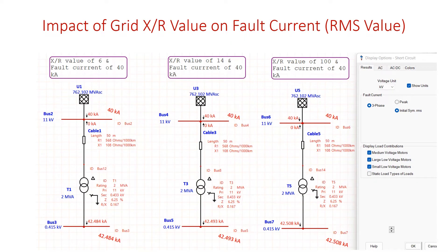In order to understand the impact of grid X by R value on fault current, I have chosen one simple ETAP model where the grid is with X by R value of 6, fault current of 40 kilo amps. I have provided one cable that connects transformer, cable with the length of 50 meter, R1 X1 value displayed here. The transformer is a 2 MVA transformer, primary with 11 kV, secondary with 0.433 kV. Impedance of the transformer is 6.25 percentage and R by X value is 0.167.